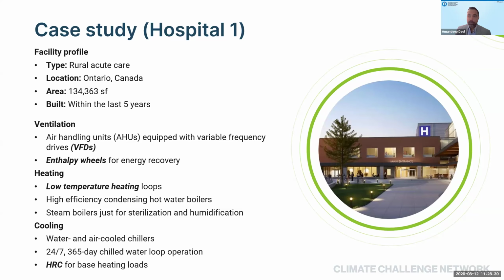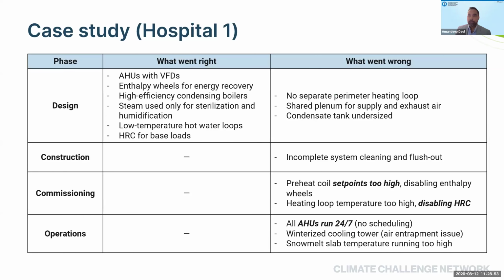The hospital was designed with low temperature heating loops, which provided an opportunity to work with a heat recovery chiller to maximize the efficiency. The hospital had condensing boilers. Steam boilers were only used for high pressure steam load, which is sterilization in the hospital. And even after all of the infrastructure, the hospital still turned out to be inefficient compared to the hospitals in the same database that we previously showed, which were built 30 or 40 years ago. This hospital couldn't even meet those energy numbers.